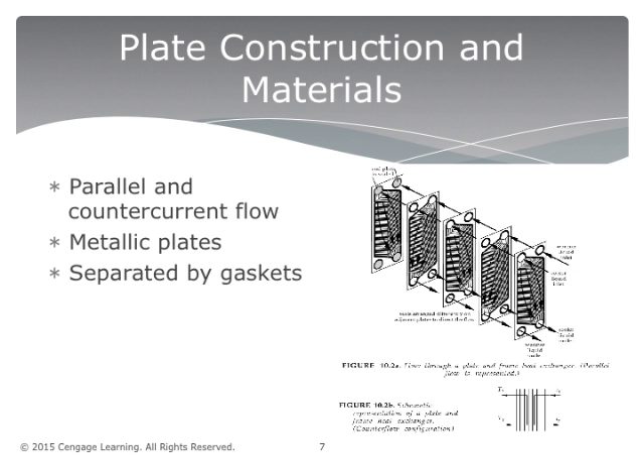Titanium is also used for its resistance to corrosion in systems containing chloride or brackish cooling water. Other materials used include nickel, zirconium, or brass alloys, as well as pure metals like copper, silver, or aluminum. The gaskets of the plate heat exchanger are used to separate the fluids. These are usually constructed of materials such as natural rubber, styrene, silicone, or butyl rubber. The construction's maximum pressure is limited by the strength of the material's frame, while its operating temperature is determined by the strength of the gasket's material.